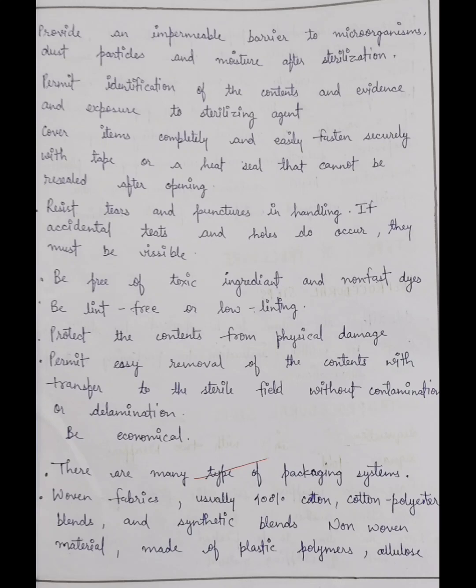Packaging must permit identification of the contents and provide evidence of exposure to the sterilizing agent. It should cover items completely and be securely fastened with tape or a heat seal that cannot be resealed after opening. The material must resist tears and punctures during handling. If accidental tears or holes do occur, they must be visible.